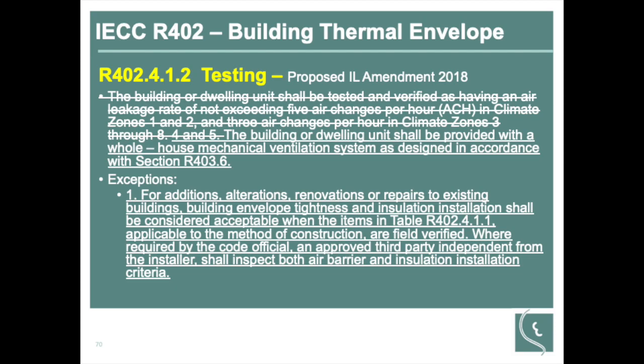This is actually a weak point that I've seen out in the field. Additions to buildings, especially with masonry walls where you've got that air gap behind your brick. A lot of times the addition will be built on and that air gap gets left there. And you've got an open hole along the entire wall with outside air in it. They had an elementary school that had that problem. They just had dehumidifiers running in the classrooms on that addition to take care of the additional air flow. So that's where this comes in to be a really important addition to the code.